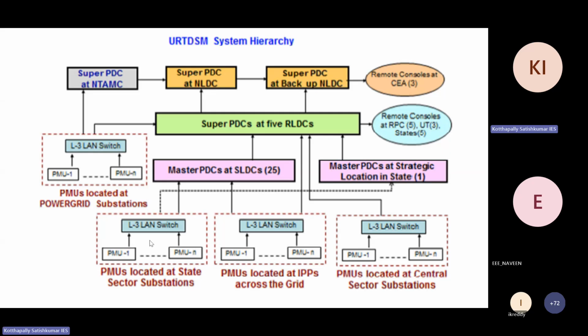And you can see there is always redundancy. This LAN switch collects 2-3 PMU's data and transmits it to one master PDC at the SLDC, and also transmits the data to the strategic location in the state. These master PDCs then transfer the data to the super PDCs, which are at the RLDCs. RLDC is nothing but regional load dispatch center.